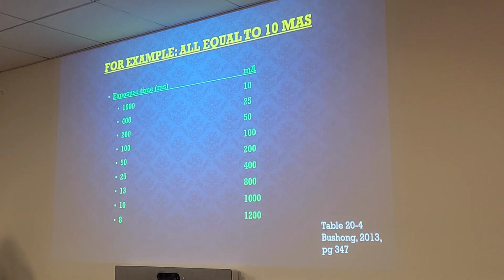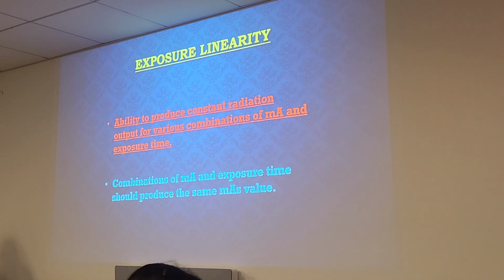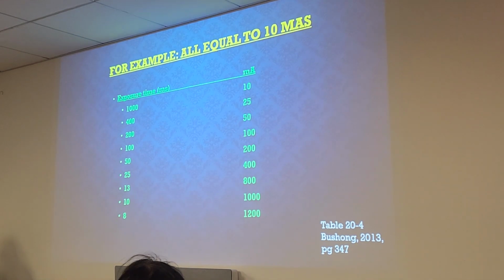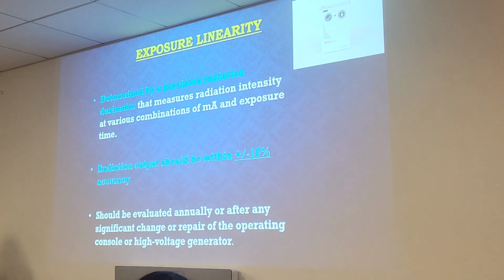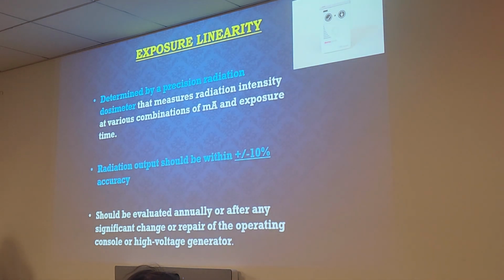Is this also within a percentage, or does it just have to be this way? Like the other ones were within 10%, is this within 1 or 2%? I think this one is within 10% as well, yes. Okay, plus or minus 10%. And he uses a radiation dosimeter for the calculations. And is that what stays in the room, always behind the lead barrier? Sometimes at clinics they'll leave it in there, sometimes they'll take it with them. It just depends.